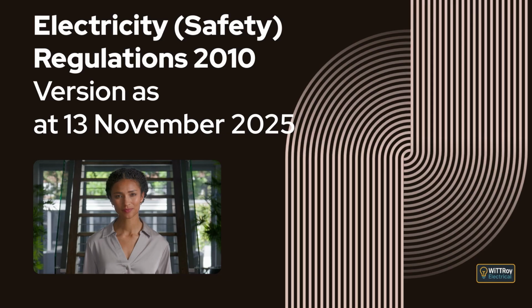Reg 75. Periodic assessments of certain installations. This regulation explains that the owners and operators of certain installations must make sure those installations are periodically assessed to confirm that they are electrically safe and comply with these regulations. It explains that this requirement applies to low-voltage installations in caravan parks, which must be assessed in accordance with AS/NZS 3001.1 at intervals not exceeding 5 years, and to low-voltage installations in boat marinas, which must be assessed in accordance with AS/NZS 3004.1 at intervals not exceeding 5 years.